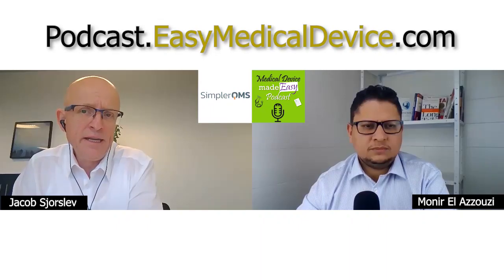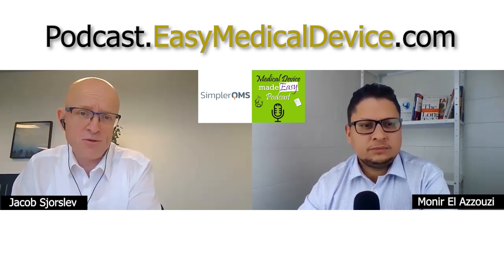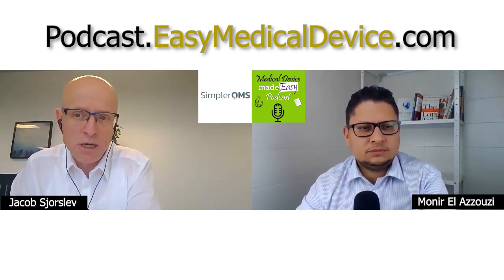But I would like to actually start with the first thing you need to do when you decide: do I actually need to do validation or not? Because you have to do a regulatory criticality assessment, where you look at whether the intended use is part of the regulation. If it is part of the regulation, then you have to do validation. And after you have decided that you have to do validation, if the answer is yes, then the next question is, do you need Part 11 compliance?